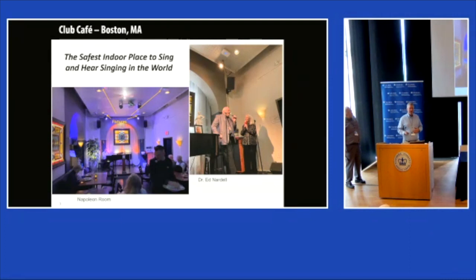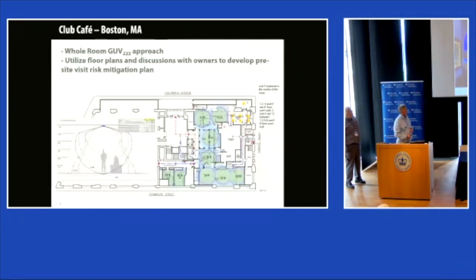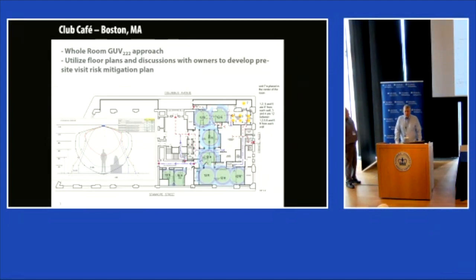This is a good example of how dosing methodologies have changed. Originally, and even to this day, the first thing we always do is get a floor plan to see how much area and volume we're looking at, and ideally ceiling heights. Ceiling heights indicate how much area a given lamp will expose. Not every fixture using a given light source is the same—the design of the lamp has a profound impact. What diffusers are chosen, what filters are chosen, what power supply drives it—it's not all the same. I like the labeling efforts we're doing with NEMA, where that will be specifically noted on each product.